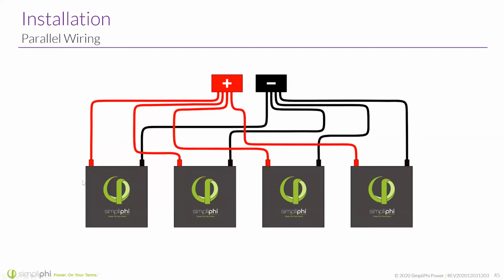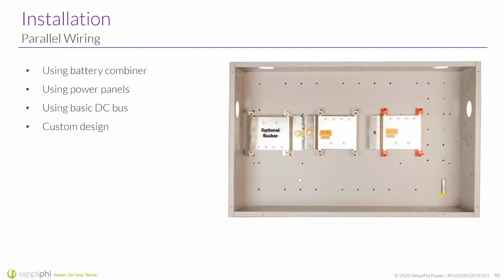We want same length, same size cables, all going to a common bus bar or connection point. This helps distribute the power evenly, makes sure we hit that same efficiency, and we don't have charge and discharge imbalances. You can use things like combiner boxes, power panels, or basic DC buses to do that connection.